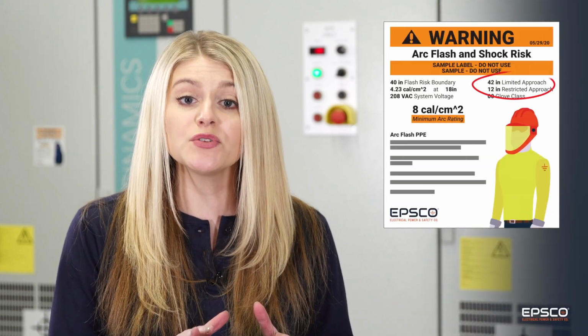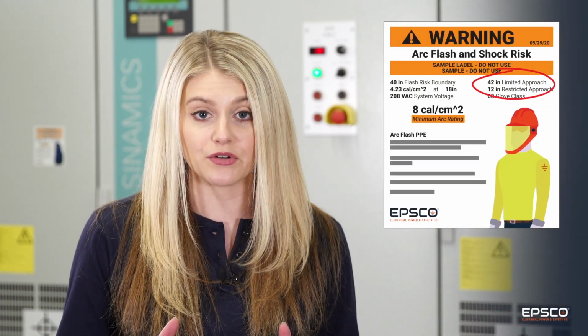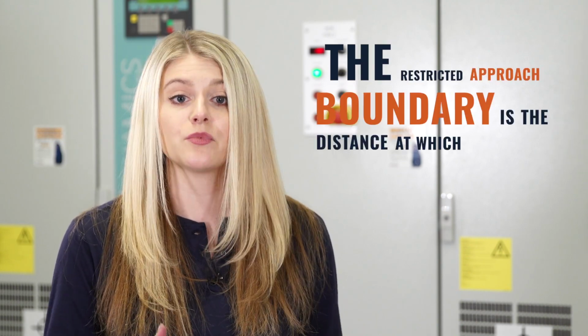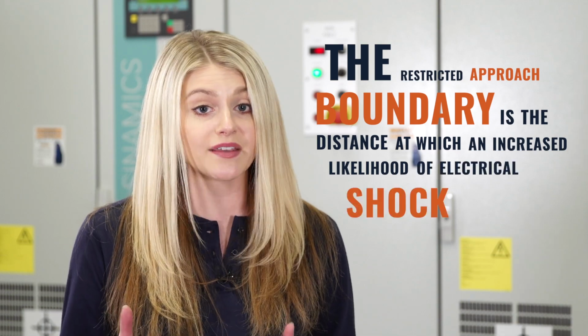Remember that the limited approach boundary is the boundary where exposed energized circuits pose a shock hazard. Unqualified individuals should never cross this boundary unless they're made aware of the hazards and continuously escorted by a qualified individual. The restricted approach boundary is the distance at which an increased likelihood of electrical shock exists. It should only be entered by qualified personnel using the proper shock PPE. Approach boundary recognition is critical because electricity can travel through air. That means you don't need to come into direct contact with an energized circuit to receive a life-threatening shock.